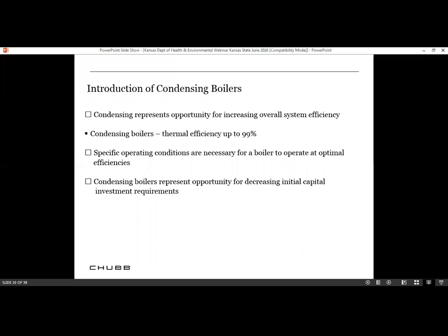I want to talk a little bit about introduction to condensing boilers. There's a lot, and we insure a lot of hospitals in the state of Kansas, and a lot of them are being retrofitted now, from the old 40-year-old boiler to the new condensing boilers. And the reason being is because the efficiency rating is so high. It's 99% on some of these boilers. But you can operate the boilers at optimal efficiency. Condensing boilers represent an opportunity to decrease initial capital investment requirements.